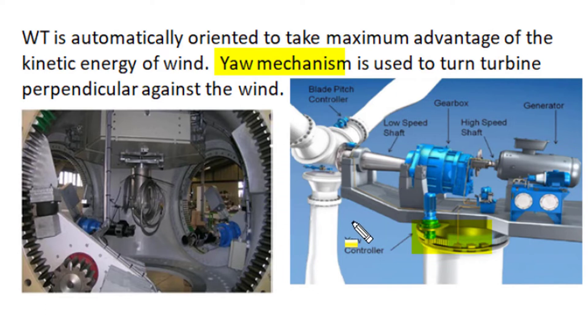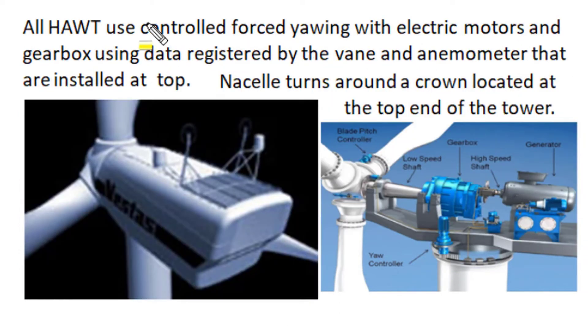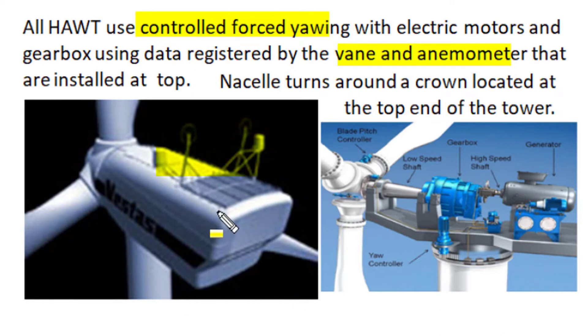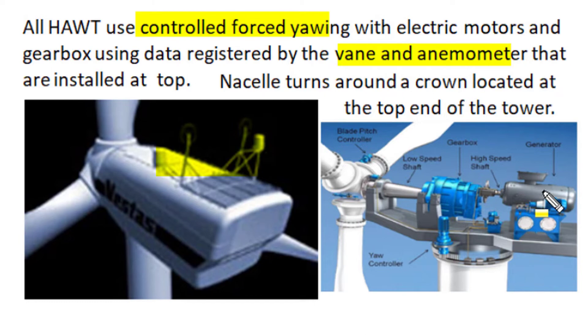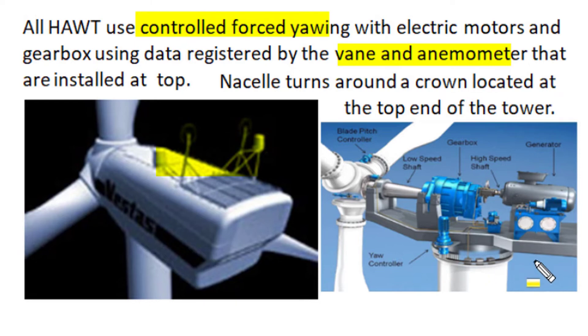All horizontal axis wind turbines have a vane and anemometer installed at the top of the nacelle body. These vanes and anemometers observe wind velocity and direction, and the data registered by the anemometer is sent to a controller inside the nacelle. A microprocessor-based controller drives an electric motor that, with a suitably attached gearbox, automatically controls the position of the nacelle bed so that the turbine blades come perpendicular to the wind blow direction. The nacelle bed turns around the crown located at the top of the wind turbine tower.